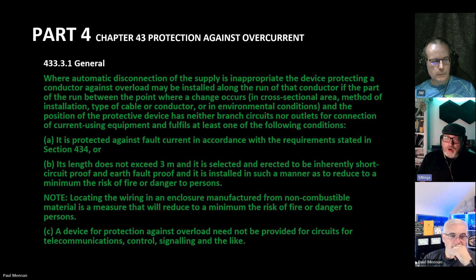It's basically it's always been there. It's just anytime the circuit run goes to a point where its current carrying capability or the sizing for things like volt drop changes, overcurrent protection needs to be considered if it's ineffective at that point. If it's not ineffective, then there's no need to change it.